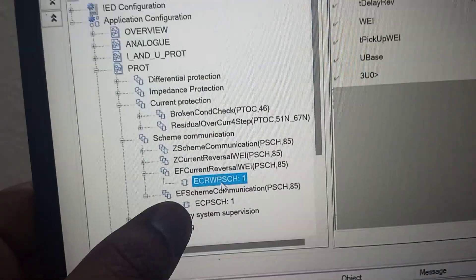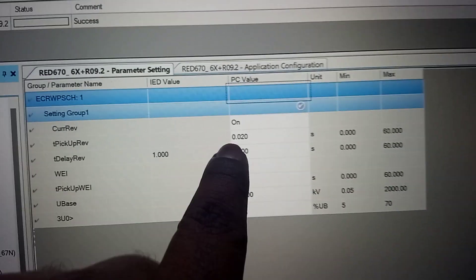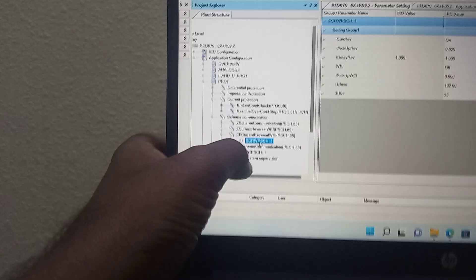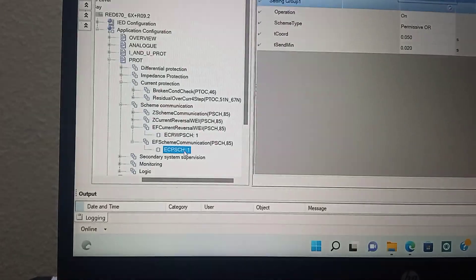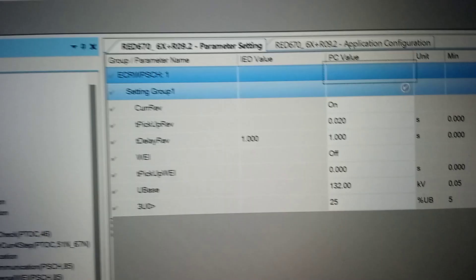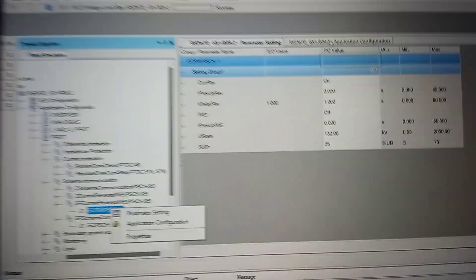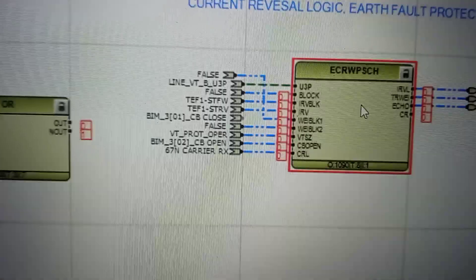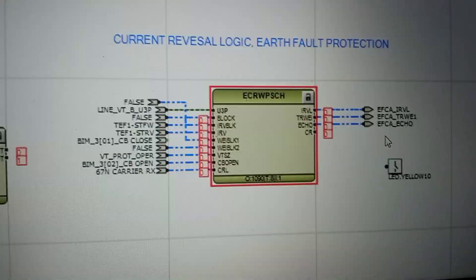Now we will check the DEF current reversal fault protection settings. The time delay is one second — this is the blocking time. The POR scheme should also be enabled. Check the function logic: POR enable. Then check the application configuration — this is the current reversal function.